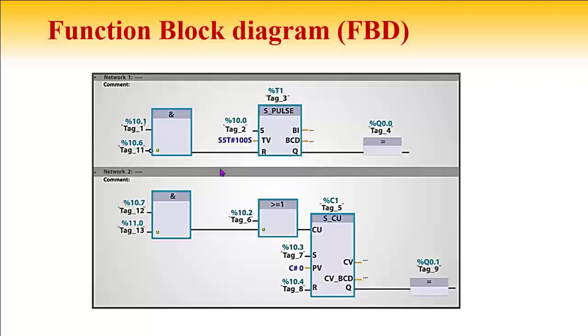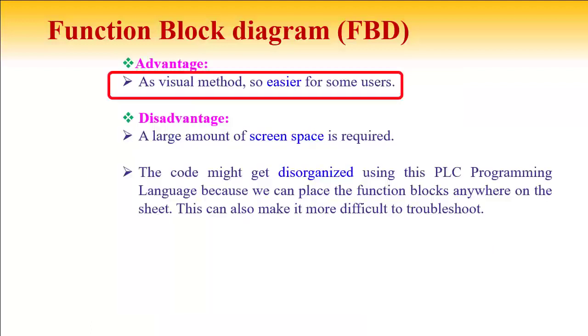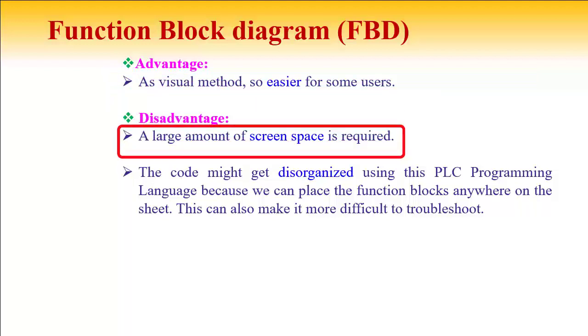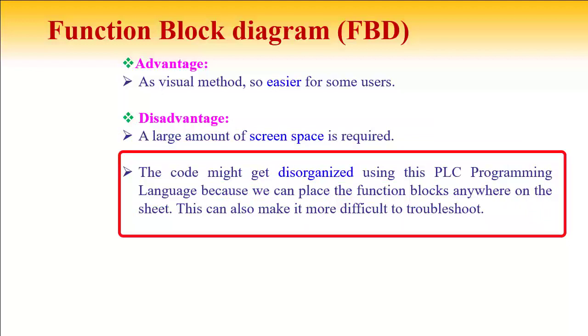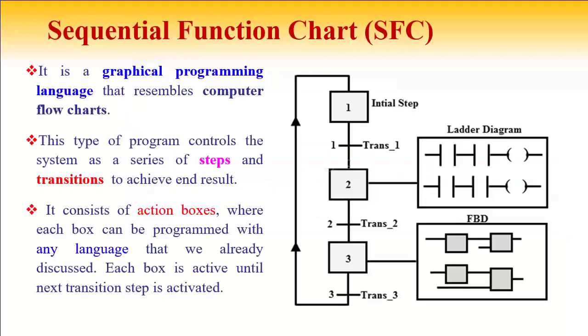Here is another example of Function Block Diagram: an AND block, a pulse timer, and an output block (defined by the equals sign). Another example shows an AND block with two inputs, a comparator block, a counter block, and an output block. The advantage of Function Block Diagram: it is a visual method and one of the easiest methods for PLC programming. Disadvantages: it requires large screen space, the code can become disorganized since blocks can be placed anywhere, and troubleshooting can be more difficult.